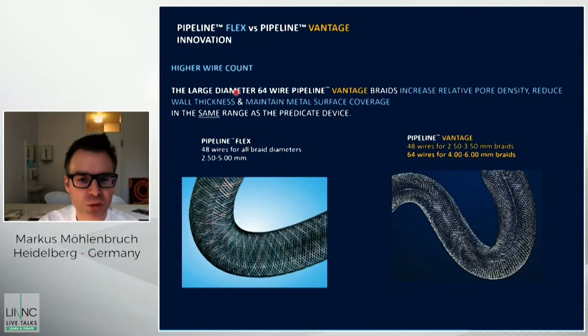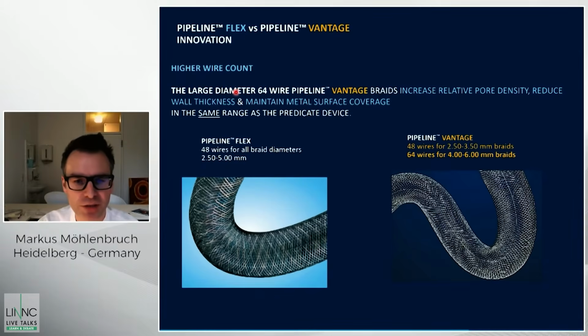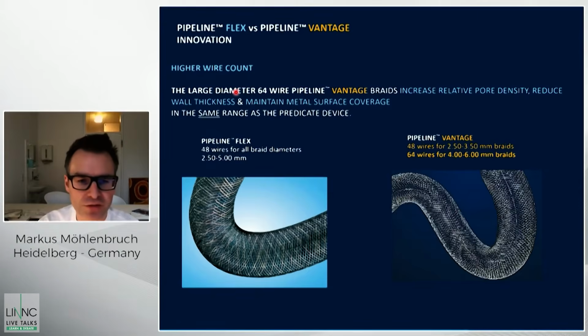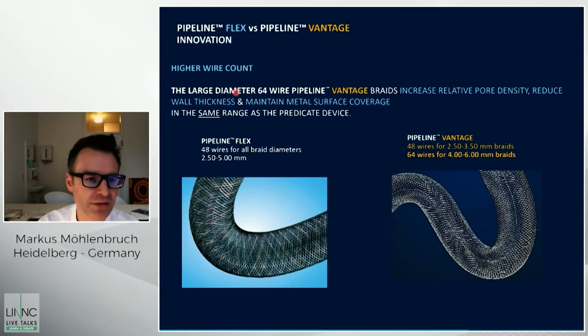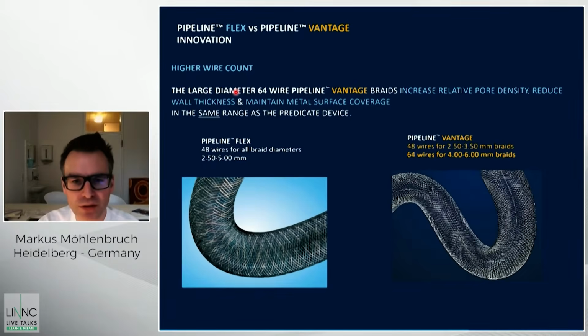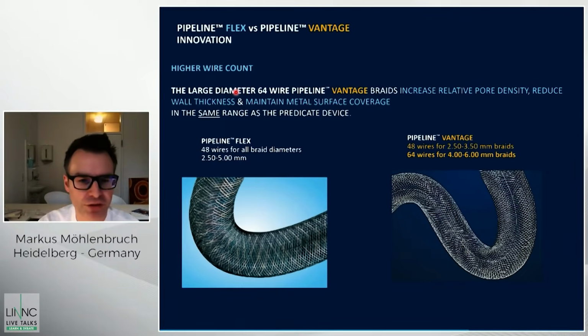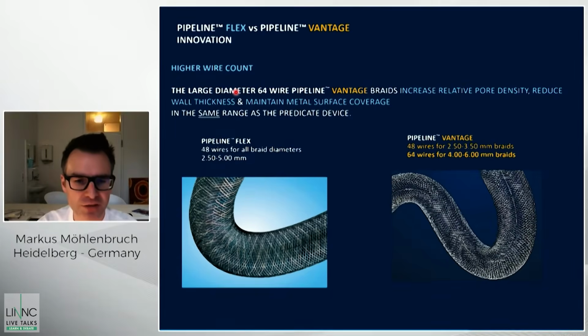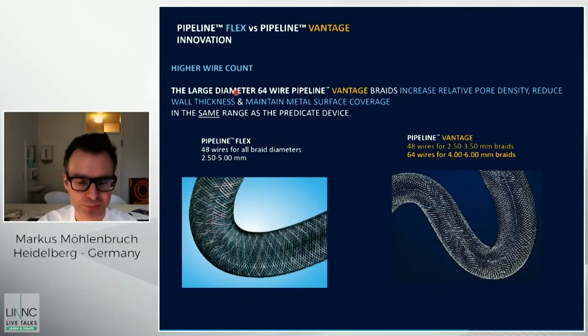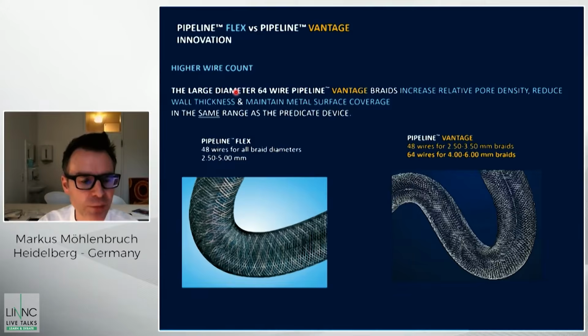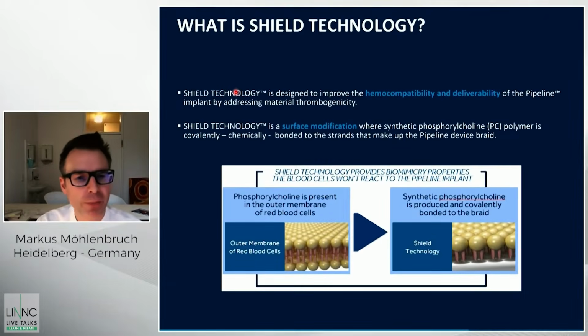There is another important feature, which is the number of wires. Larger diameters of the Pipeline Vantage consist of 64 wires, whereas the Pipeline Flex is composed of 48 wires. The higher number of wires increases the relative pore density and maintains the metal surface coverage, especially if you treat larger diameters like 5 or 6 millimeter, compared to smaller diameters where you usually have a higher rate of metal surface coverage. The Pipeline Vantage, of course, has the same or similar Shield technology as the Pipeline Shield in order to improve the hemocompatibility and the deliverability.